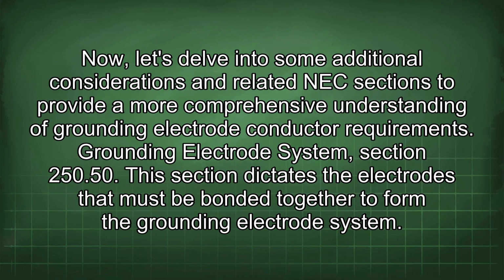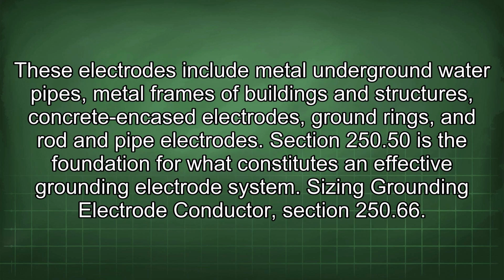Now, let's delve into some additional considerations and related NEC sections to provide a more comprehensive understanding of grounding electrode conductor requirements. Grounding electrode system, section 250.50. This section dictates the electrodes that must be bonded together to form the grounding electrode system. These electrodes include metal underground water pipes, metal frames of buildings and structures, concrete encased electrodes, ground rings, and rod and pipe electrodes. Section 250.50 is the foundation for what constitutes an effective grounding electrode system.